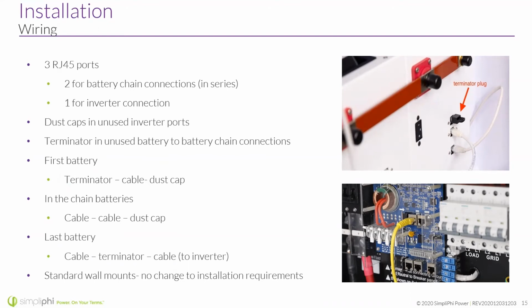Terminator in unused battery to battery connection, so this would be on each end of the battery connections. So to give an example, let's say the first battery would have a terminator, then it would have the cable to the next battery and a dust cap in that unused inverter port. Every battery in that chain would have a cable coming in to one of the battery ports, a cable going out of one of the battery ports, and a dust cap because you're not using those inverter connections, and the last battery in the system.